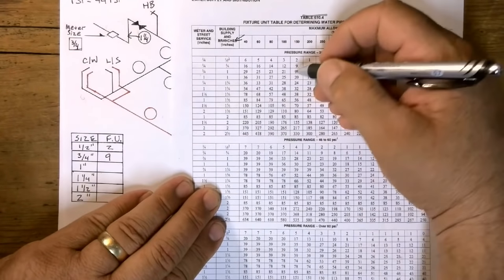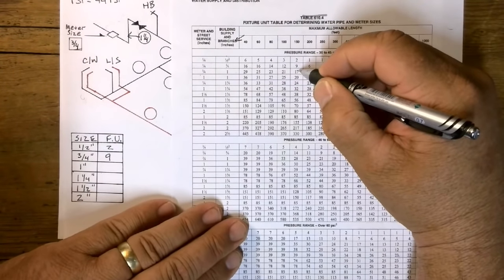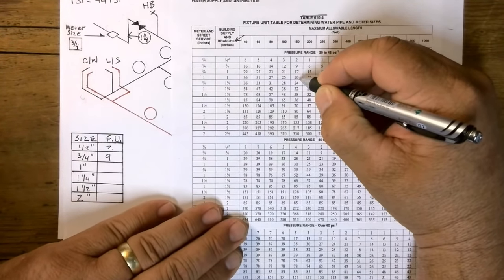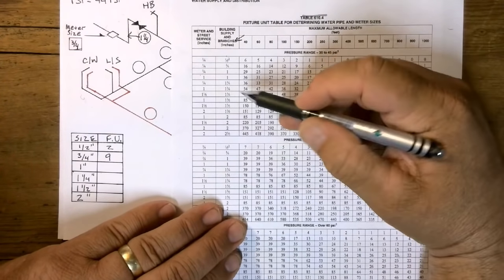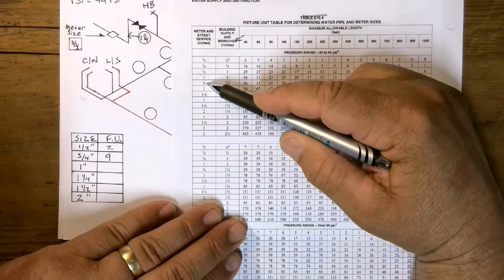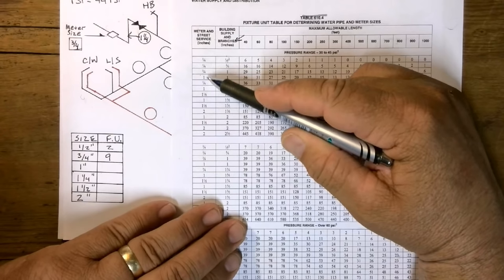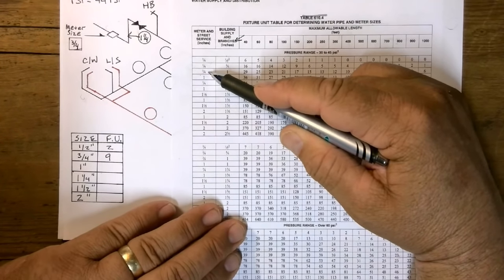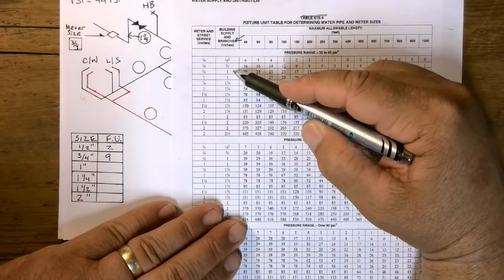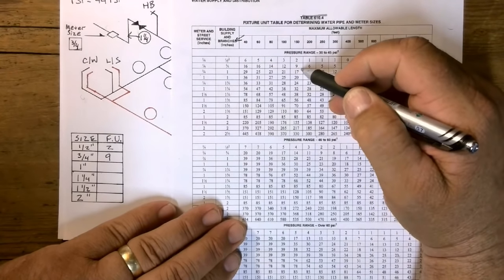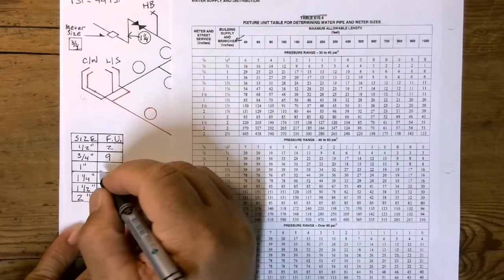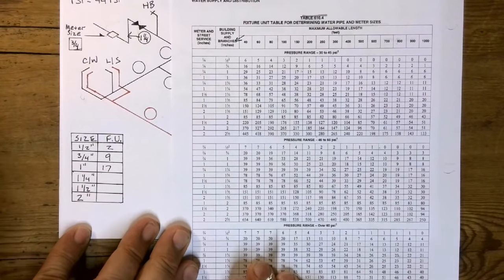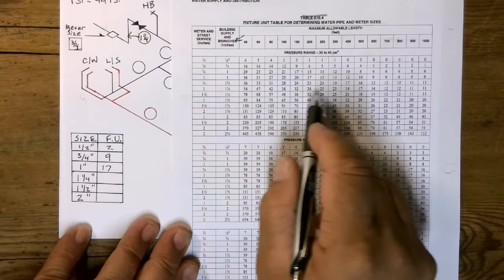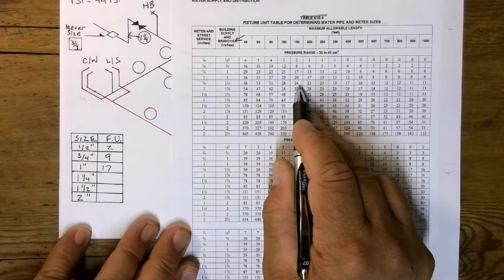Well, which one of these am I going to use, right? 17 or 20. Well, what size is my meter? 3/4. So for a 3/4 meter, not a 1-inch meter, for a 3/4 meter, my 1-inch pipe at 150 feet is going to be 17. So I can run 17 fixture units. And then the 1¼, we already know it's 24.